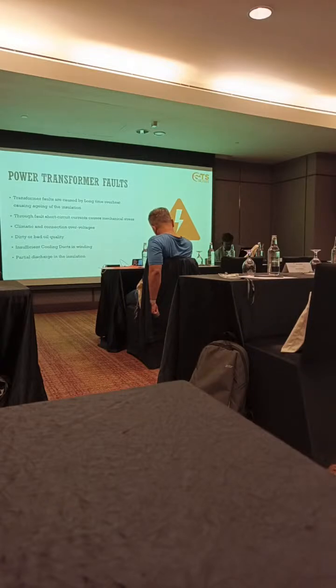So in both ways the oil will be used. Another case: if the oil absorbs moisture, what will happen? With aging, as time goes, the transformer oil will start absorbing moisture. Once it absorbs moisture, its dielectric strength weakens. Once the dielectric strength weakens, the insulation level between the windings and the core will also go down, which ultimately leads to transformer failure. So this is another case.